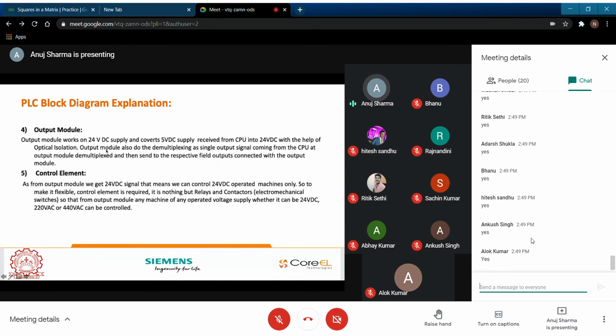And you have the output module, again PIQ and output module. Your output module works on 24 volt DC and converts the 5 volt DC supply from CPU to 24 volt DC with the help of optical isolation again. The output module also does the demultiplexing. So here it is saying about PIQ that it does demultiplexing, parallel to serial, and provides particular demultiplexed data and then sends it to the respective field output. For parallel computing, your output module is capable of converting the data that came from CPU, checking which machine this particular output is concerned to, and sending it to that output.